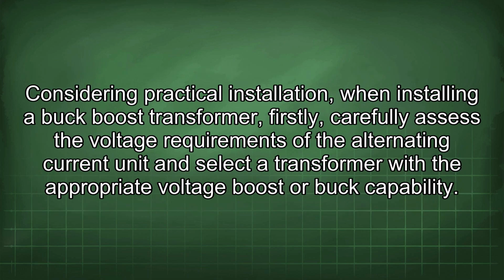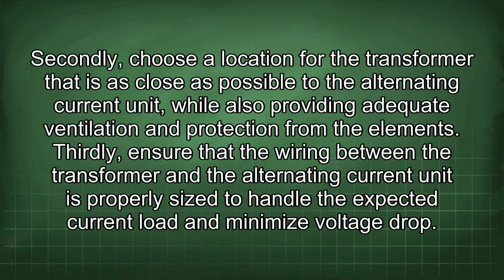Considering practical installation, when installing a buck-boost transformer, firstly, carefully assess the voltage requirements of the alternating current unit and select a transformer with the appropriate voltage boost or buck capability. Secondly, choose a location for the transformer that is as close as possible to the alternating current unit, while also providing adequate ventilation and protection from the elements. Thirdly, ensure that the wiring between the transformer and the alternating current unit is properly sized to handle the expected current load and minimize voltage drop.